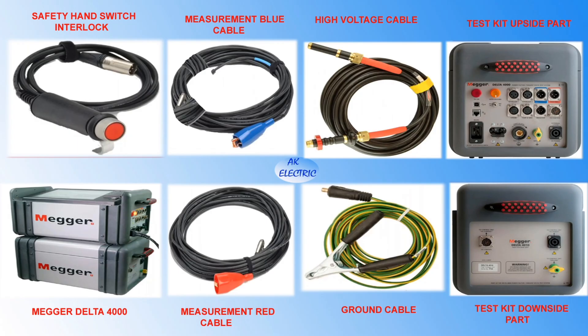This is the testing kit called Megger Delta 4000, which is used for power factor testing for transformer windings, bushings, etc. The testing kit accessories shown include: safety hand switch interlock, measurement blue cable, high voltage cable, measurement red cable, and ground cable.